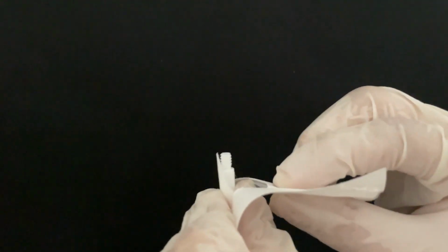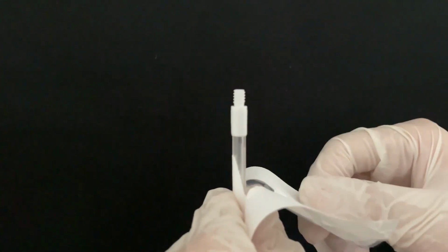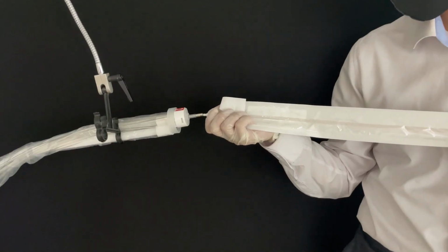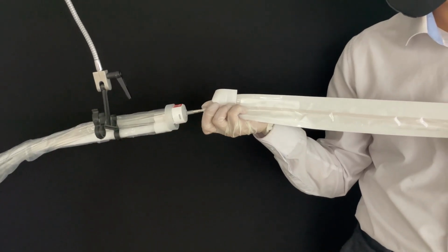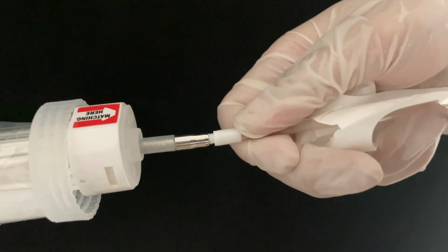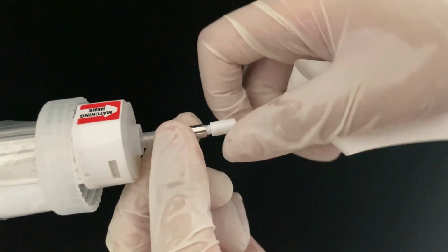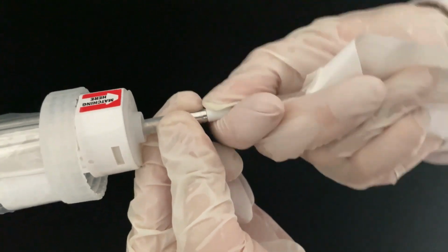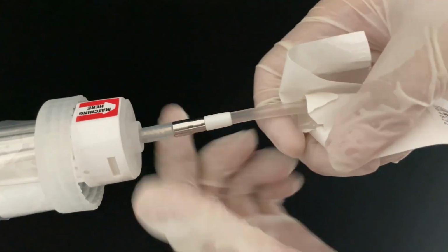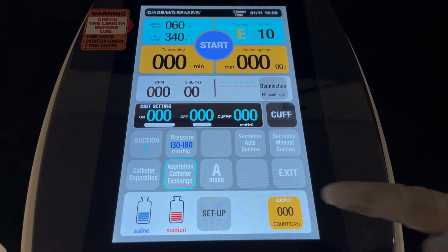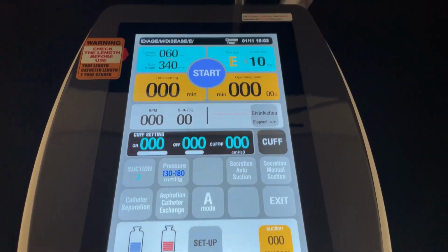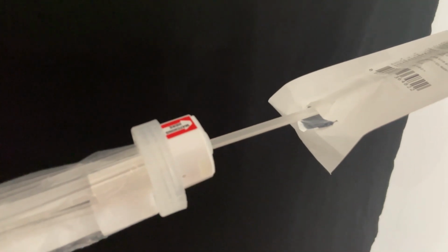Take a new aspiration catheter from a sterile bag. Connect the aspiration catheter to the connection port by twisting the white tip of the catheter clockwise. Make sure the connection is tightened. Press the aspiration catheter exchange button again. The device will automatically pull back the new aspiration catheter.